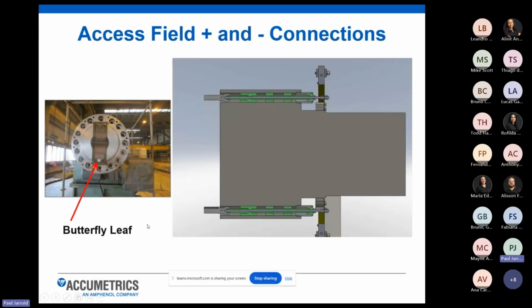So this is a cross section of what the coupling flange of the brushless exciter looks like on the right. And then the image on the left is the generator coupling flange, which is identical looking to the exciter. So they couple these 2 pieces together. And underneath that, there is what they call their butterfly leaf assembly, which is your field windings. Your copper field winding leads are broken out on the back side of each coupling flange.